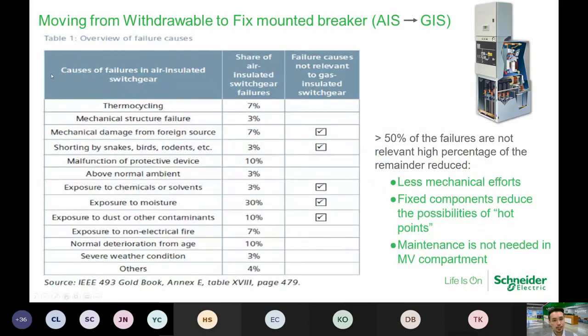Right, so there's this one chart taken from the IEEE 493 Gold Book. All right, so it tells about what the benefits are for switching from air insulated switchgear to gas insulated. So you can see by using air, these are all the different possibilities of failures, for instance, shorting by external influence, mechanical structure failures, and they actually put down a percentage in here from the IEEE Gold Book. But when it comes to gas insulated switchgear, you can see all these factors are actually being eliminated. All right, so by adding up, it actually sums up to as high as 50%.